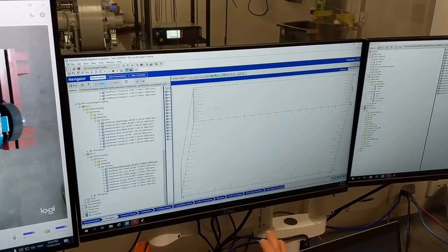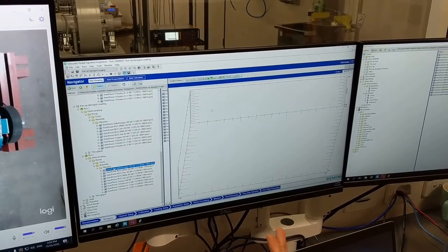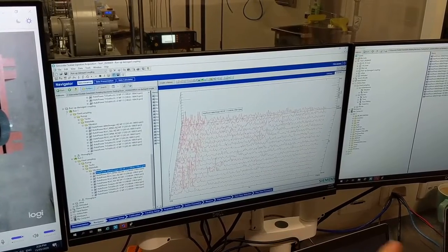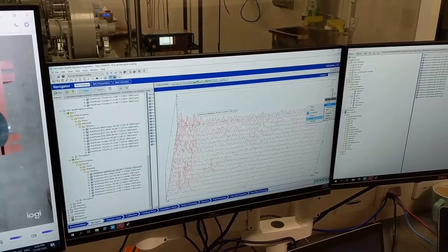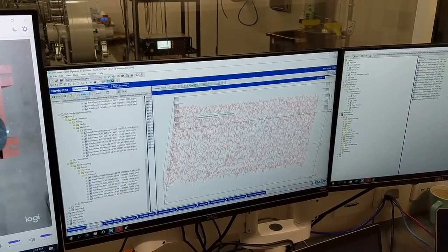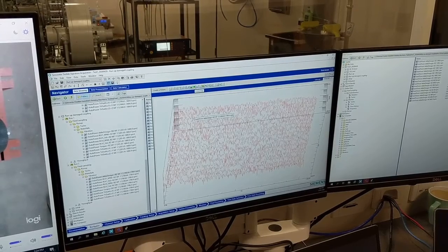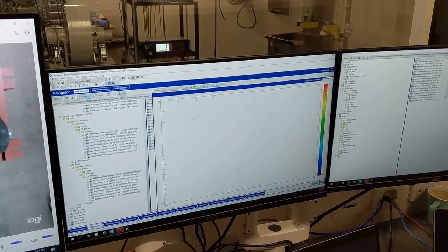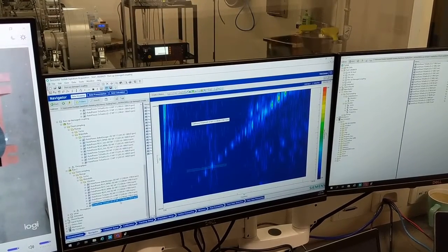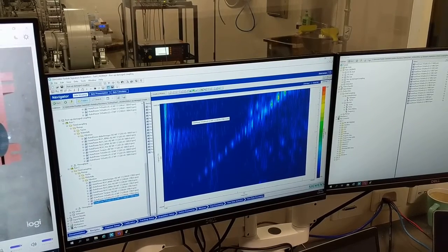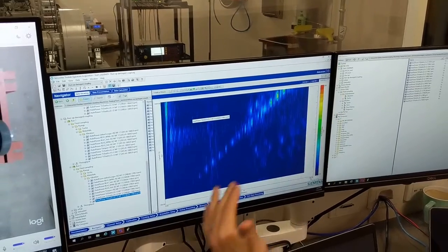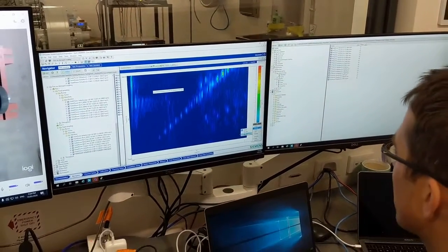So that's a new waterfall, for example, that it's an alternative to a colour map. So I can take this measurement data and drag these into this area here. I can move over here and change the format from amplitude to logarithmic scale, so you can see these individual waterfalls at 100 RPM increments. More intuitive maybe is to show that effectively from above with a colour map display, and if I choose in this case to take the auto power spectrum from the Z direction of the accelerometer, which is in the direction of the shaft, now you can see some activity within this, what's referred to sometimes as a candle diagram.